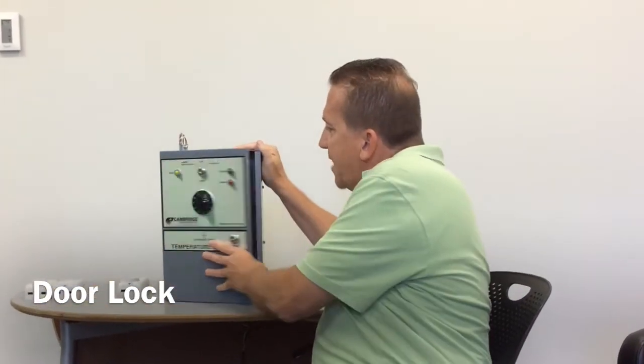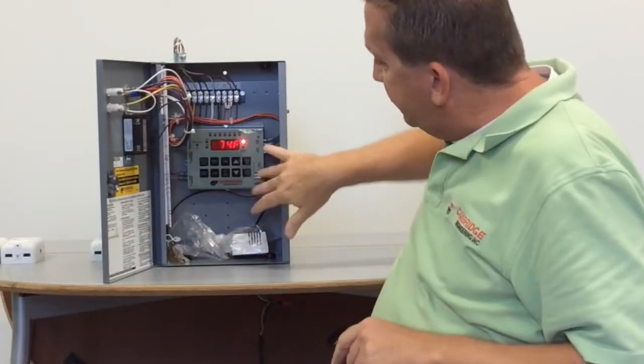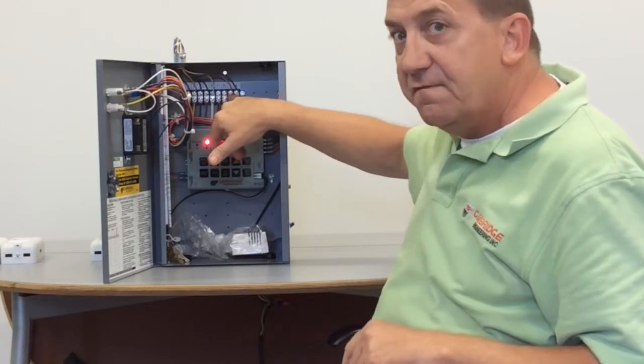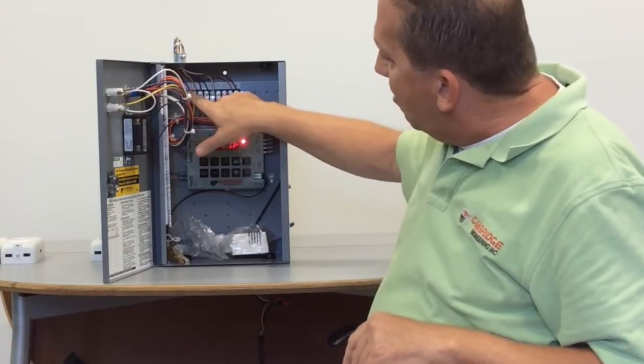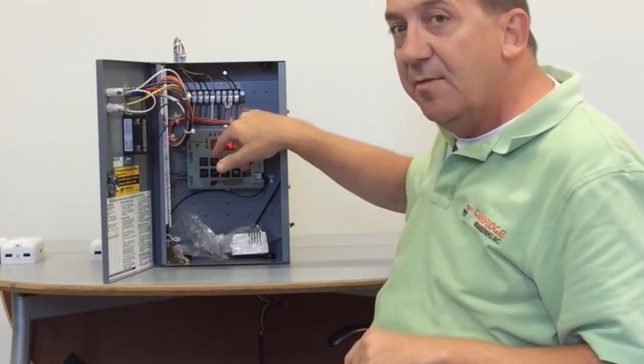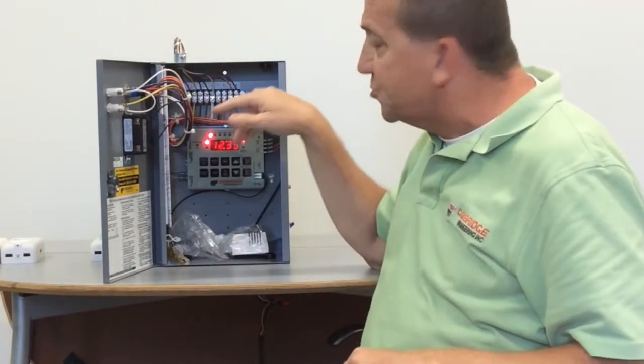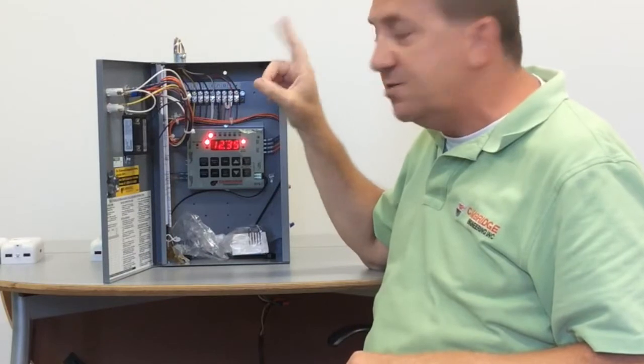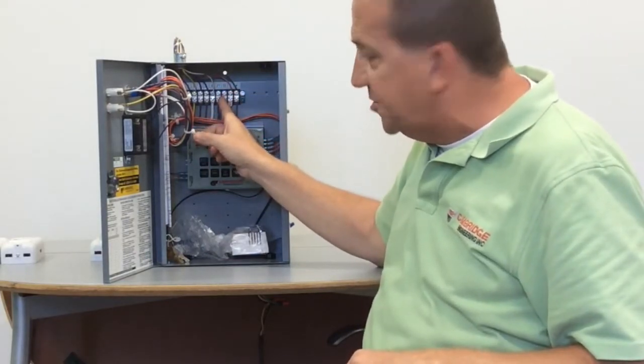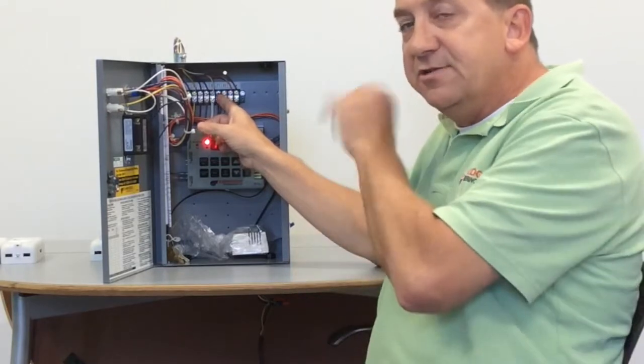Then there is the door lock. Now, if you open the panel up, what you're going to see is your TSS thermostat. You're going to see your terminal block and this is the block that is used for your field connections. You have R, H, F, A, B, Z1, Z2, G, and W, but now all these terminals will be up top in the heater terminal block as well, with the exception of Z1 and Z2. Z1 and Z2 is only located downstairs in this panel.